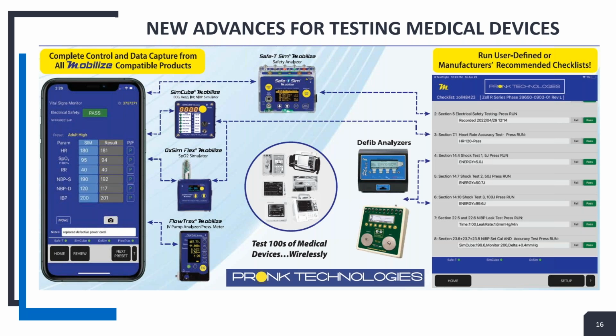Now, what's interesting with the defibrillator analyzers is you also have to do some pacing tests, so we'll skip ahead so you can see that. What's interesting on the pacing test is you have to set the analyzer up. It wants you to make sure you set the analyzer properly for the pacing test. We talked earlier about setting it up for pacer. You don't need any defib.